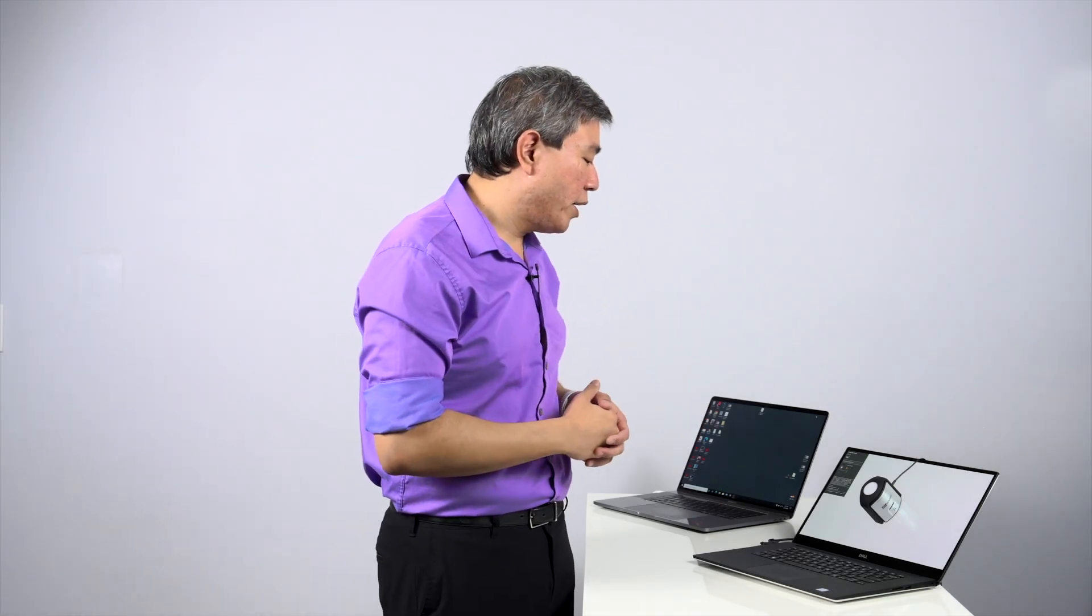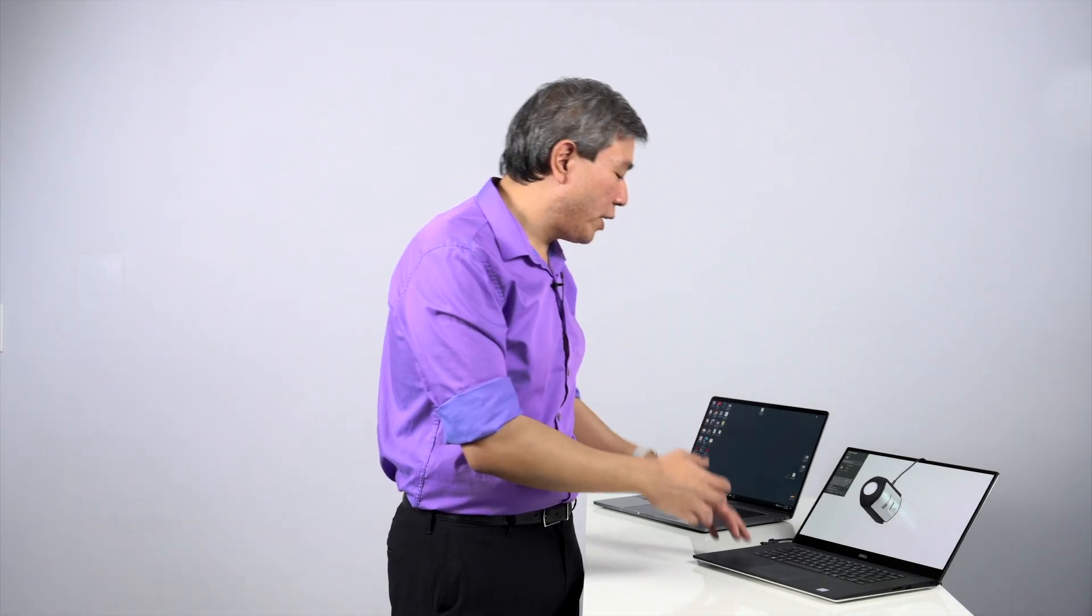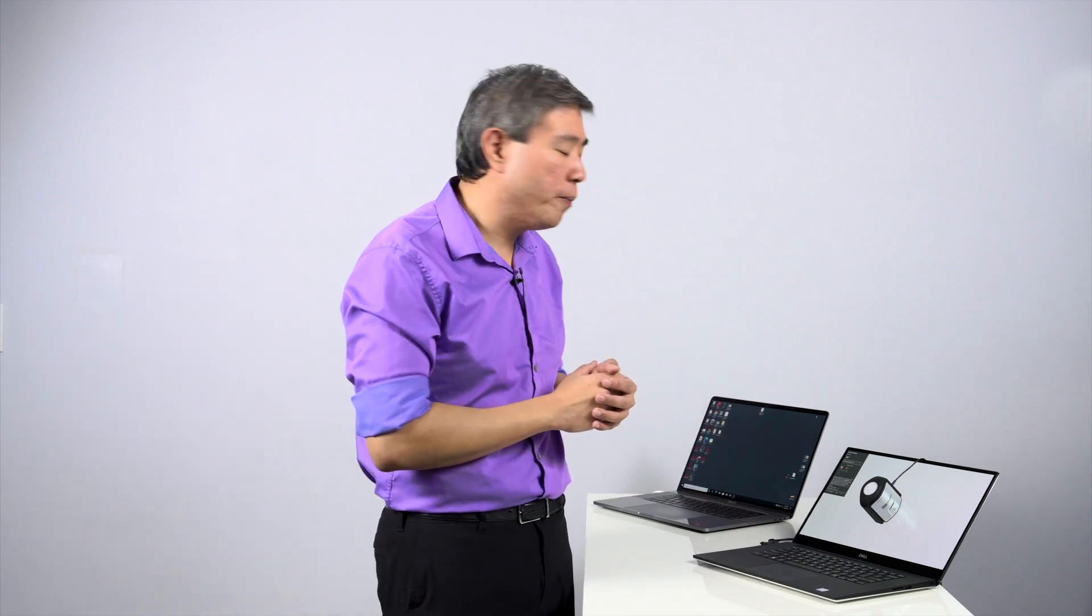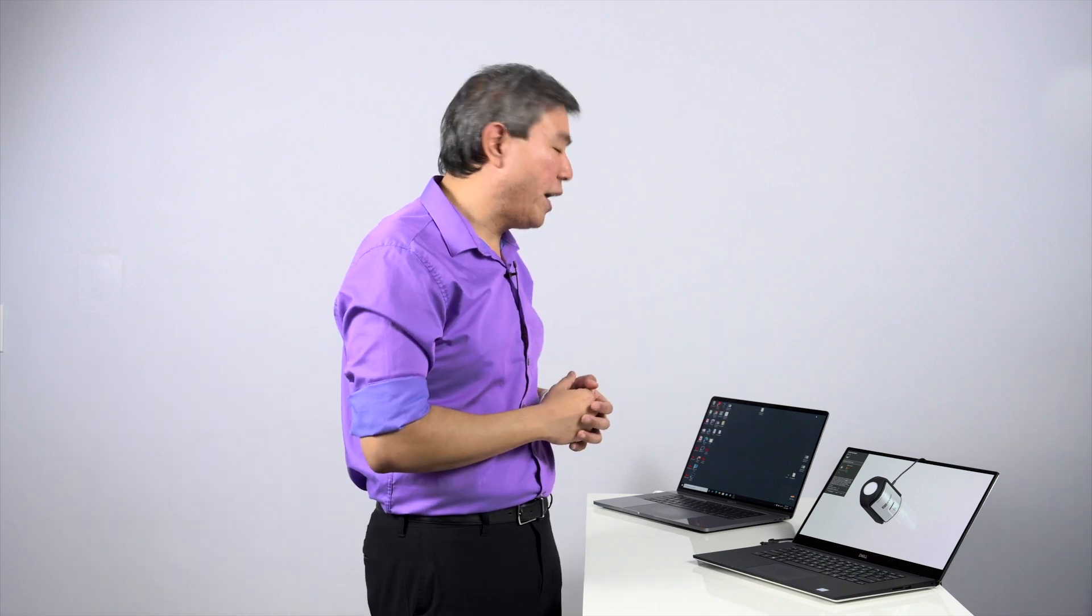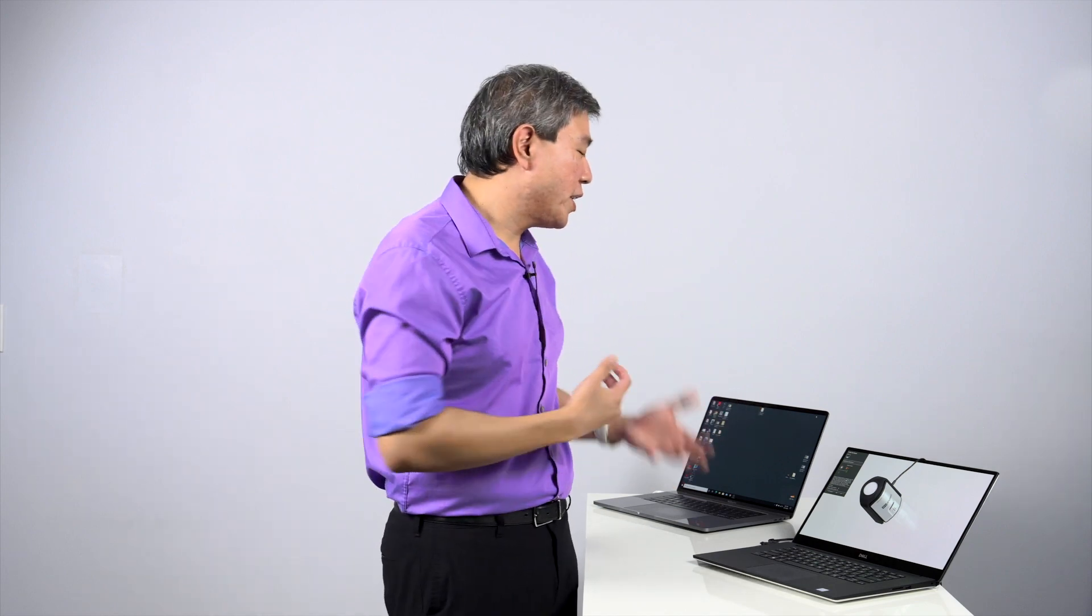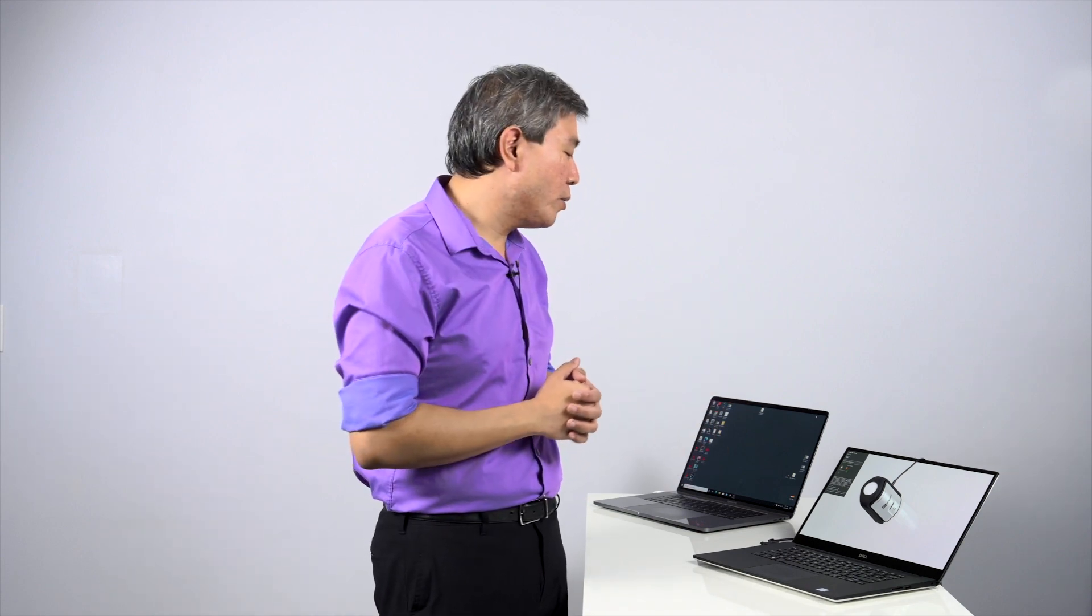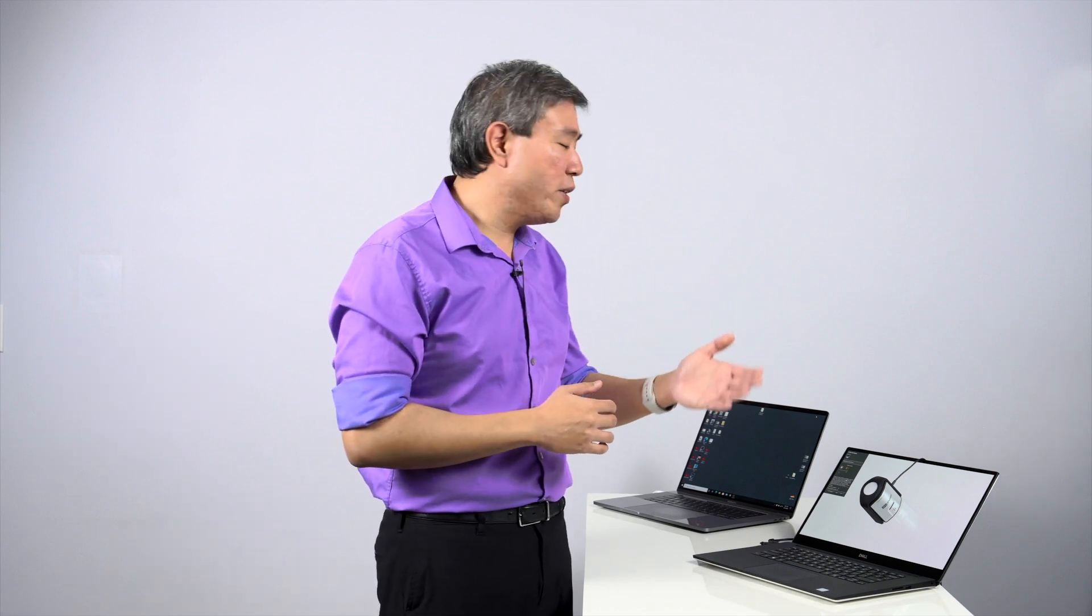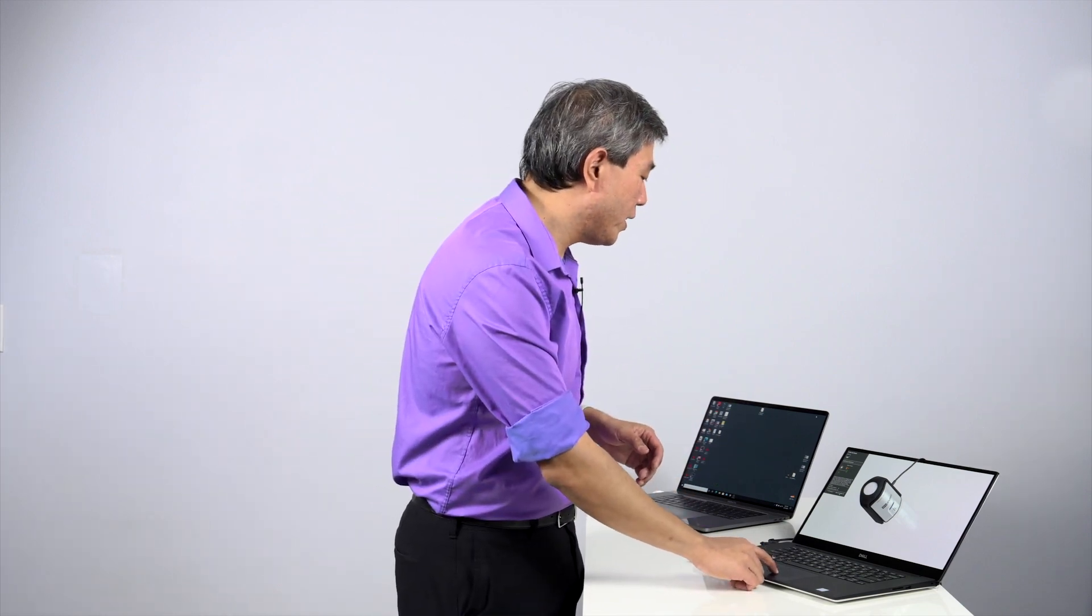Another thing to keep in mind is that because you're running on a laptop PC and you're relying on these notches system, it is okay if you don't land exactly on the value that you have chosen. In this case, I have the value at 92. It's not quite 80. But 92 is within the range of 80 to 120 candela. And as long as you can get within that range, you're okay. The only thing you have to do is choose whether you want the lower end or the upper end of that range. I'm happy with 92. From here, click on next.